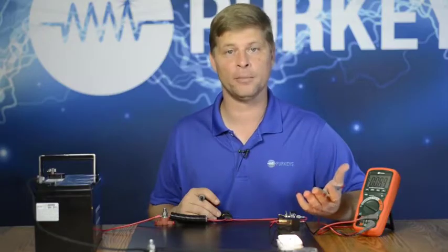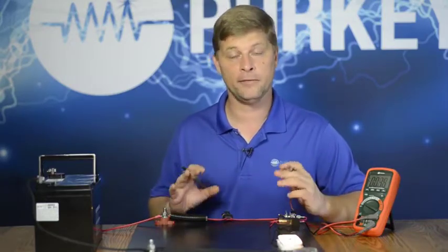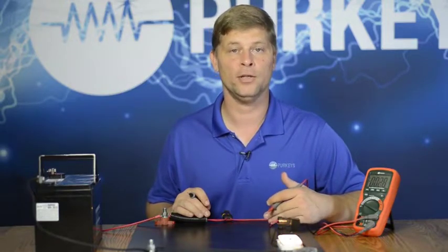All these types of tests can be easily performed using your Purkeys multimeter. It makes it very easy and very accurate to do these tests to know exactly what you have. The biggest thing you got to keep in mind when you are using your voltmeter: you cannot have voltage drop if you don't have current flow, so you have to make sure you have the circuit energized and the load. And your voltmeter will flat talk to you and tell you exactly what's wrong with that system.